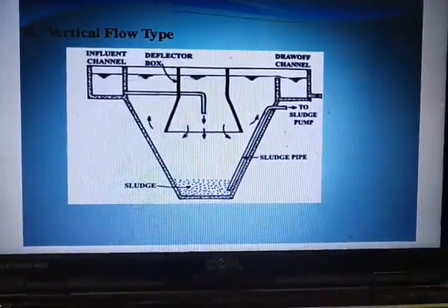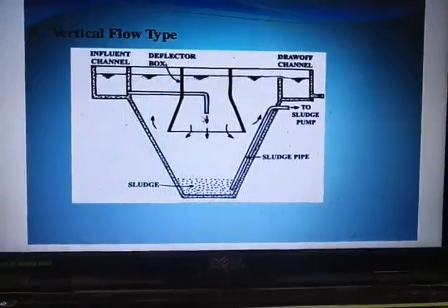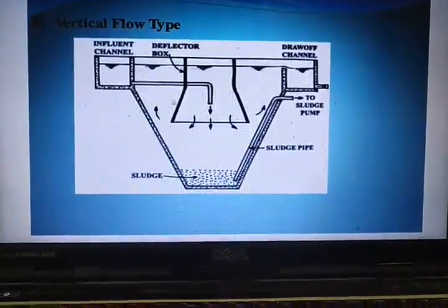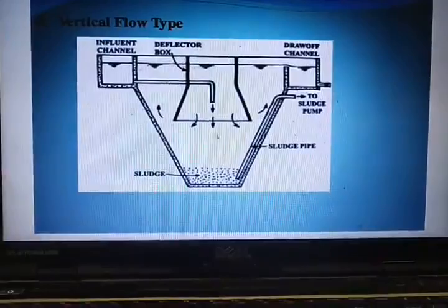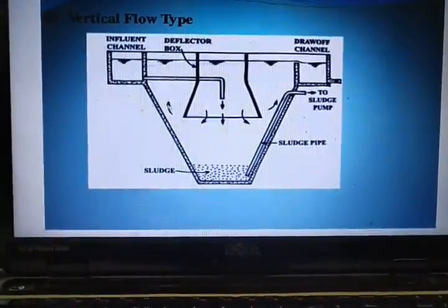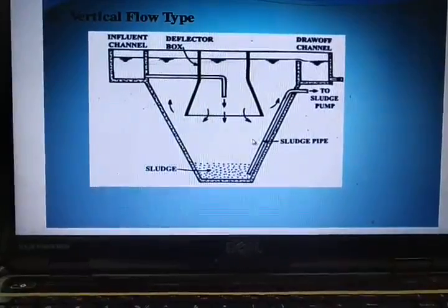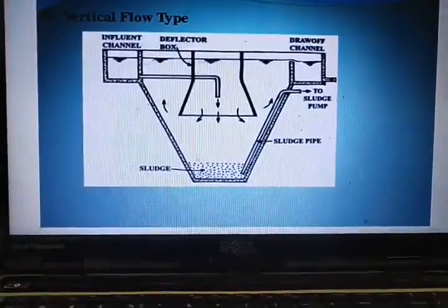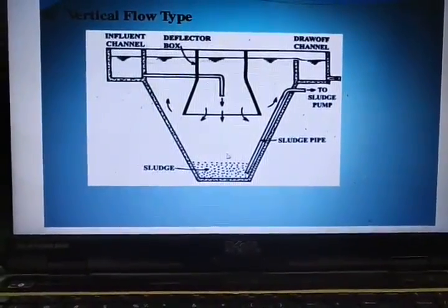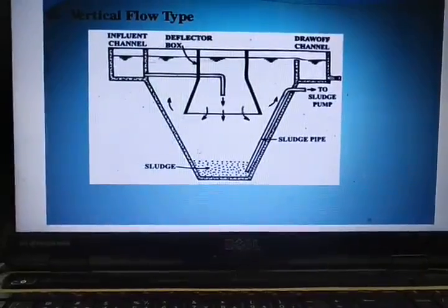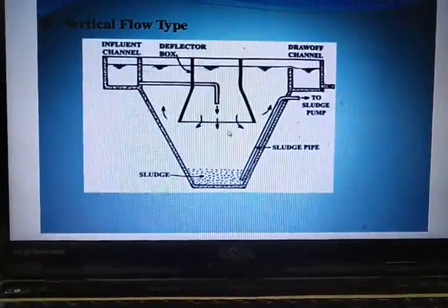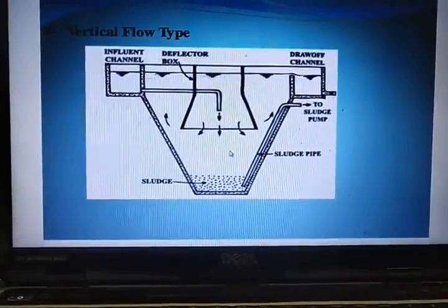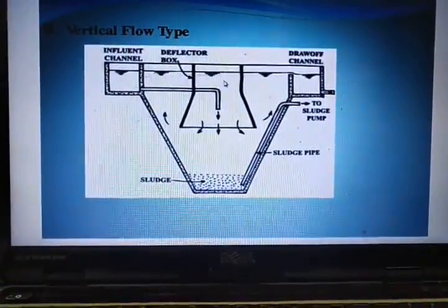Here the water will enter vertically through this pipe, and it will have a circular path like this, so that the velocity will be reduced as you move down, thereby allowing the sludge or sedimentation to happen in this small area. So this hopper bottom is provided again in order to reduce the velocity of the flow so that the particles can easily settle, okay.